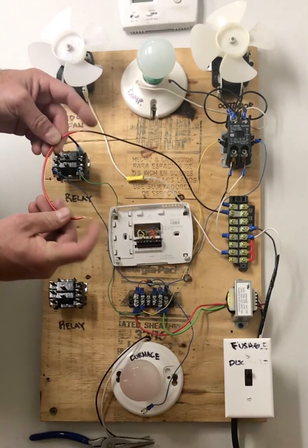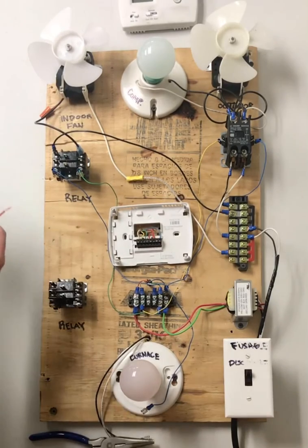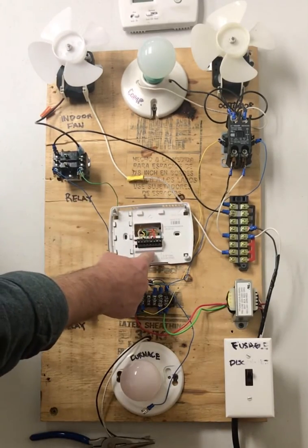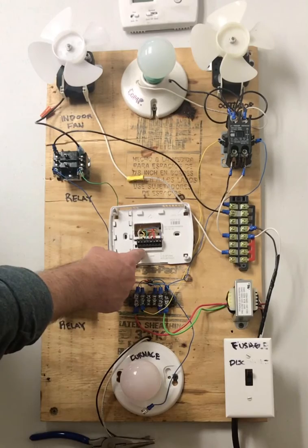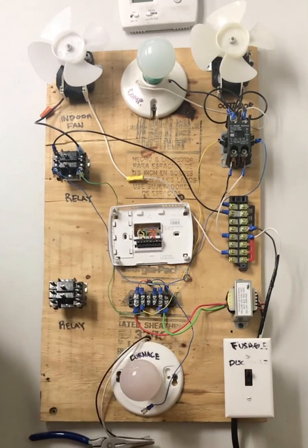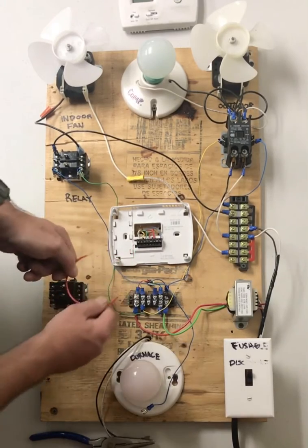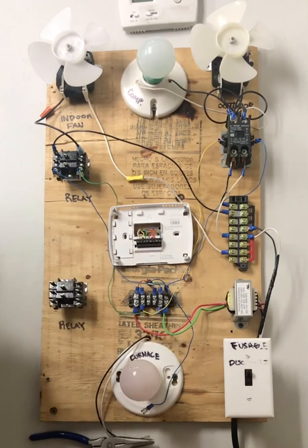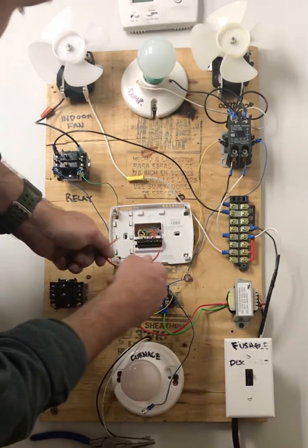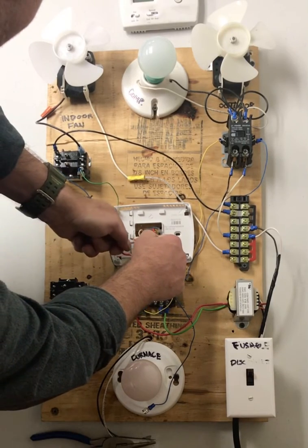You strip the ends off so you've got the copper wiring exposed, and then you simply do the job of the thermostat, which, if its job is to send power from the R terminal to the G terminal when you're making a fan call, then you simply take your wire and you place it from R to G. Now there's little metal screw heads right here, and that's all you've got to do is place your jumpers there. So you take one, you put it on R, you take the other, you put it on G.